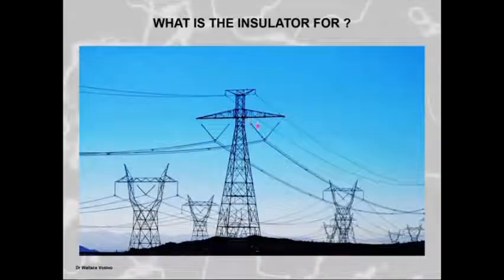Now, that insulator that is sitting there is there for a very, very good purpose, because it has to insulate this high voltage. These conductors are at high voltage, in this case most probably 600 or 800, most probably 600 kV DC, and this has to be insulated from ground potential, because the structure here is at ground potential with good tower footing resistances. The structure is mechanically designed to take the weight and all the various stresses put onto the structure by this conductor being suspended from the insulators from the actual tower structure. Now, this insulator needs to insulate this high voltage from ground potential.